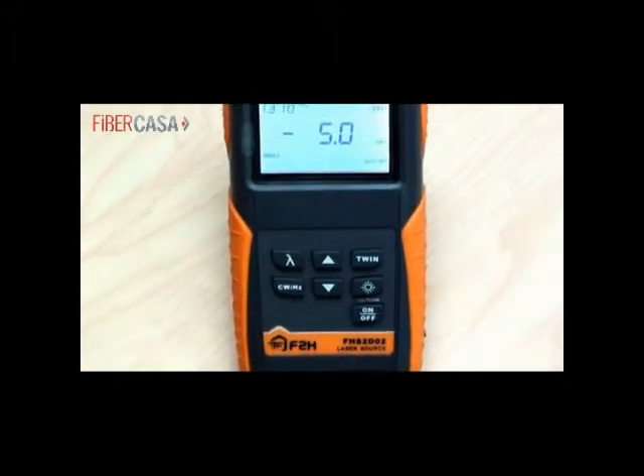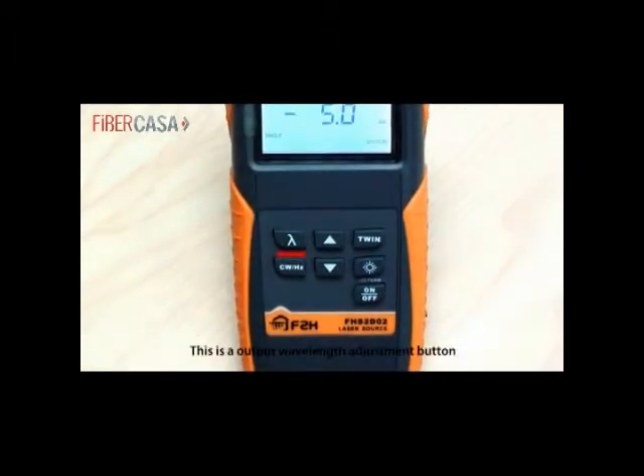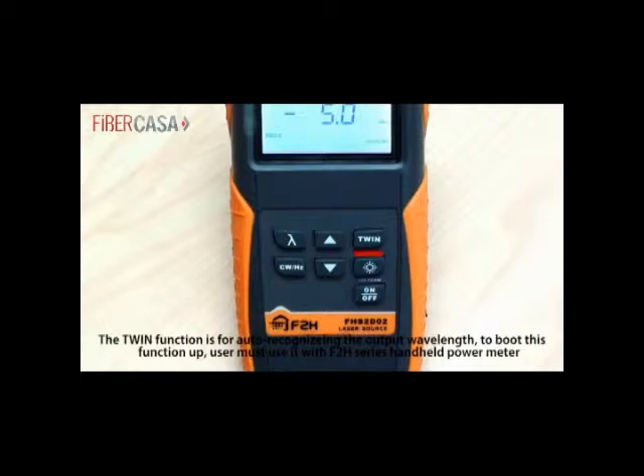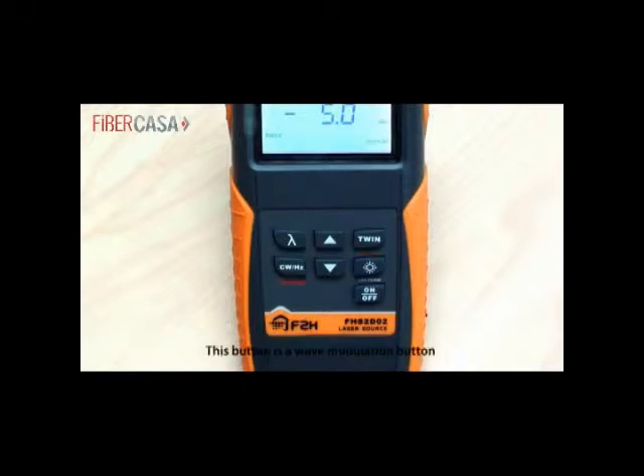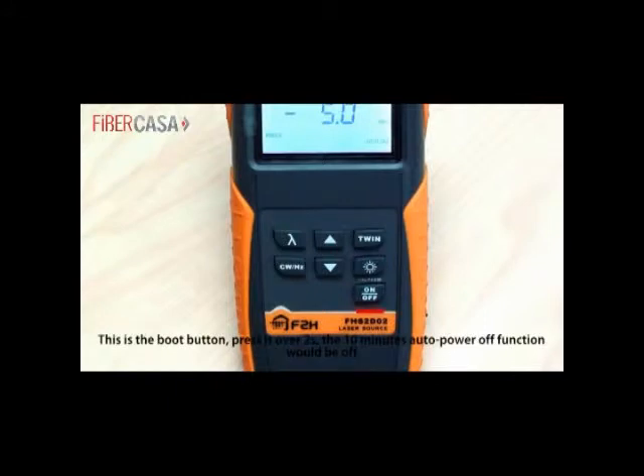Button function. This is the output wavelength adjustment button. This is output power up adjustment button, 0.1 dB per step. The TWIN function is for auto-recognizing the output wavelength. To boot this function up, user must use it with F2H series handheld power meter. This button is a wave modulation button. This is output power down adjustment button. This is a screen backlight button. This is the boot button. Press it over 2 seconds. The 10 minute auto power off function would be off.